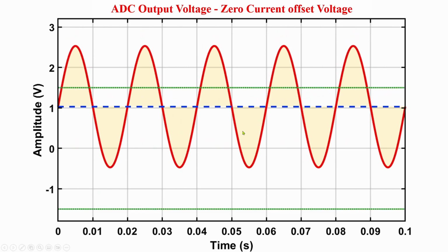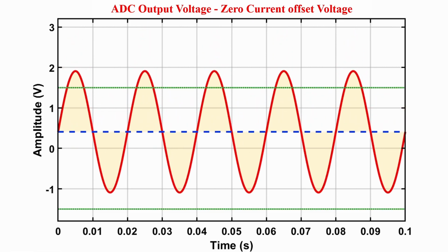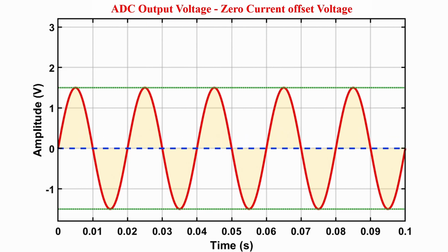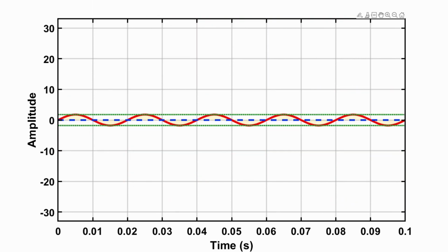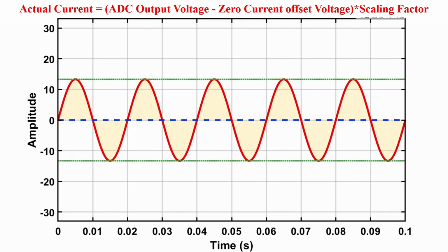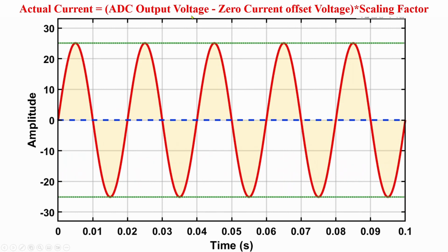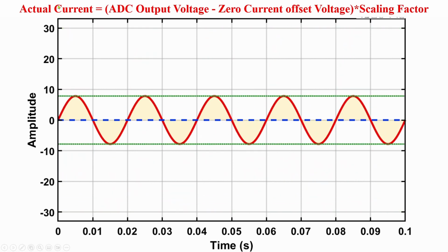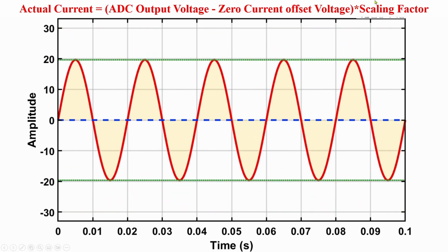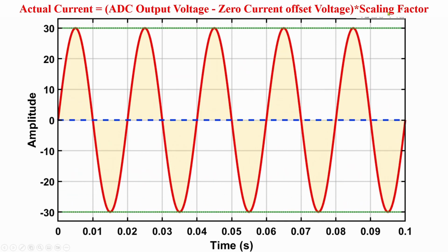To reconstruct the actual current, the first step is to remove the zero current offset voltage. Once this offset is removed, the waveform becomes centered around 0. The next step is scaling. Here, the offset removed voltage signal is converted into actual current. For this, we multiply the voltage signal with the proper scaling factor. In this way, the measured sensor voltage is reconstructed as the actual current waveform.